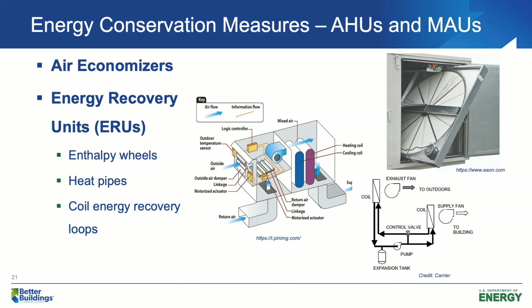All right, here we have a few more energy conservation measures for air handling units and makeup air units. The first one is airside economizers. When it is cool and dry outside, it takes less energy to cool outdoor air than return air, so it makes sense to take 100% outdoor air and exhaust all return air out. This is the idea of airside economizer. Exhaust all the return air and take all the air from outside.